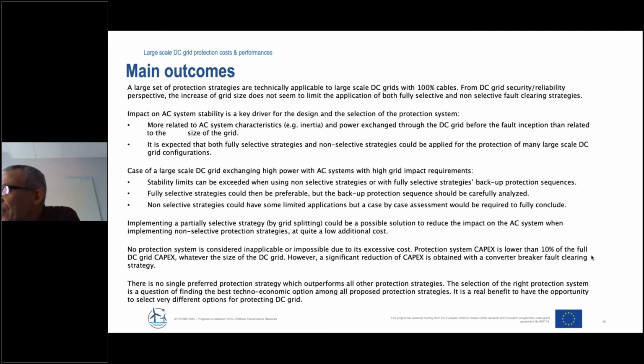I think that at least you need to have a quite good idea of what the grid will be in the first steps. We do not really need the full picture, but at a certain level you need to know the different steps of initial development, mainly to clarify the constraints coming from AC system grid impact requirements. Once we've clarified that, we can select the best protection strategy. Then, of course, if the grid evolves afterward, there are several ways it could evolve: it could be an evolution in size, an evolution of the offshore system, or also an evolution towards more inland penetration.